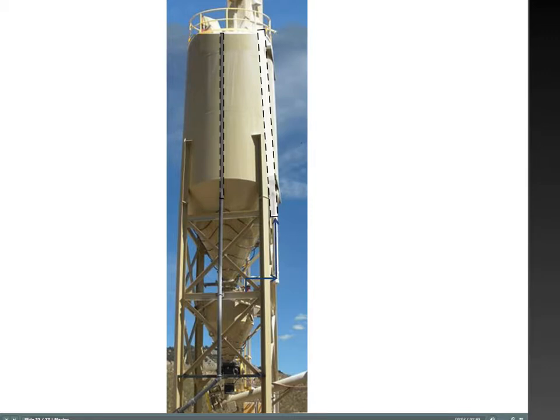Normally, the weight on the weigh pod scale decreases slowly as material flows out of the pod through the vane feeder. The control system adjusts the vane feeder speed for the flow rate required. Normally means that the silo is not being filled while the plant is running. Storage silos may need replenishing many times during production. Filling a silo can sometimes take as long as an hour.